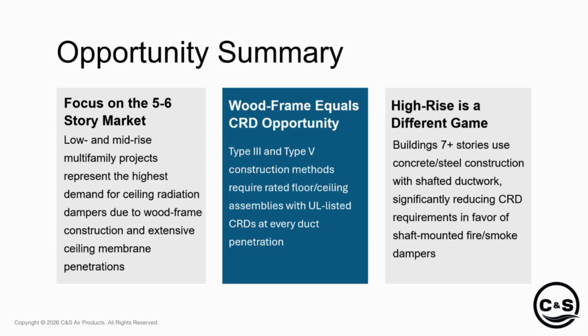So there is one dynamic ceiling radiation damper out there on the market right now. But about that specific design, and I'm going to get into some intricacies of the code here, there's UL 263, which is the test for all these different floor ceiling assemblies. The damper manufacturer that decided to do this dynamic ceiling radiation damper tested it that way. So it's one floor ceiling design that's dynamically listed, but it's very restrictive. You have to have double layer sheetrock. You have to fully insulate the ceiling radiation damper, I think it was with R11. And then you also have to have hard duct throughout the entire system.